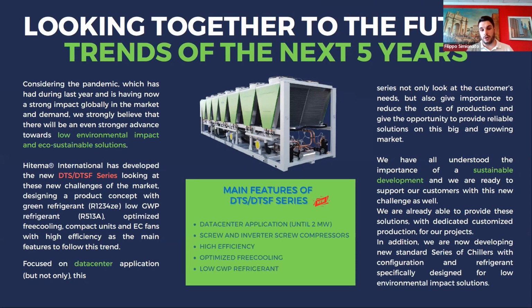Basically it is based on high efficiency, the possibility to have optimized free cooling, and as said, the possibility to also use low GWP refrigerants. Generally, this series was born for data center applications, but we can also follow and use and produce this unit, which is also useful and available for several process cooling applications in the market.